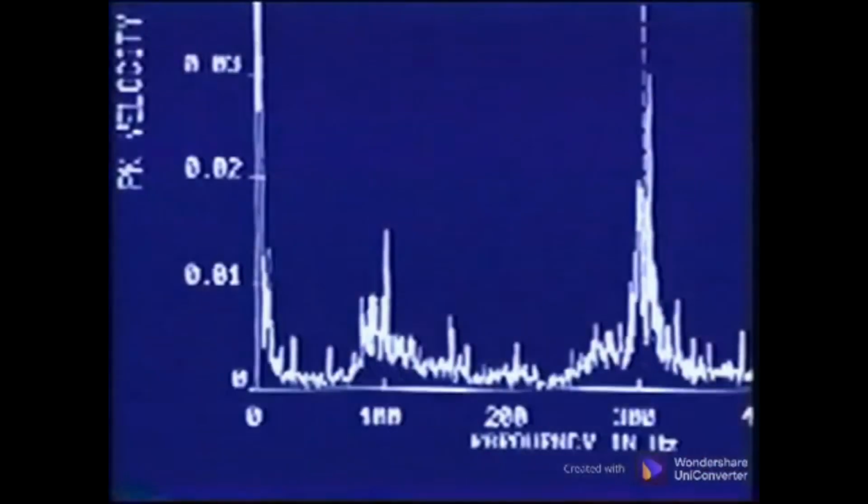Of course, the testing should be done while there is a load against the teeth, so it will resemble the gear load as it is meshing. The key here is that this resonant frequency will be modulated by sidebands spaced at shaft speed.